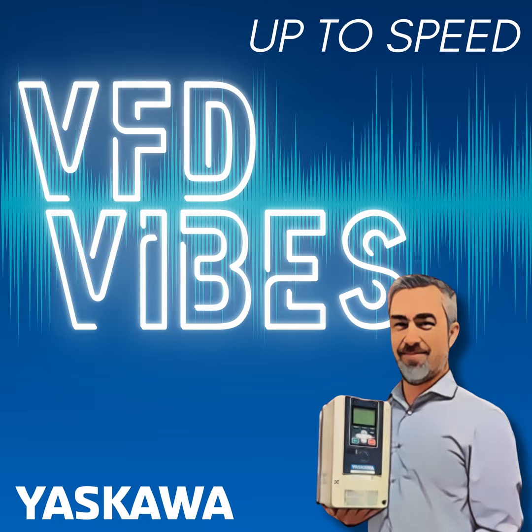When we say these type ratings, are these NEMA ratings, or how do they compare to NEMA ratings? NEMA is a set of guidelines. And when I say type 1 or type 12, I'm referring to UL ratings, which are more official guidelines, where NEMA is kind of recommendations. They both mean very similar things, but as a UL shop, we are going to provide an enclosure with a UL rating. That makes sense.